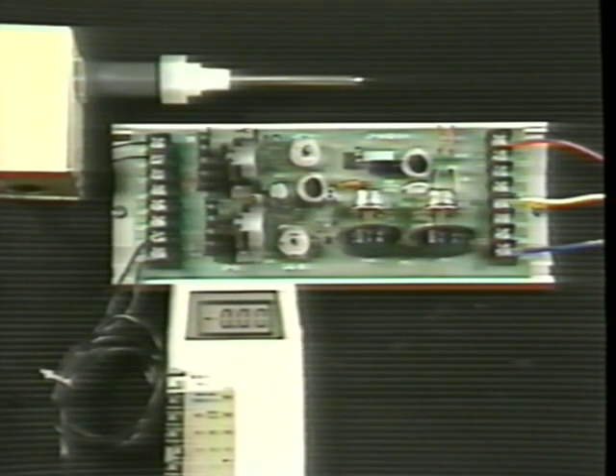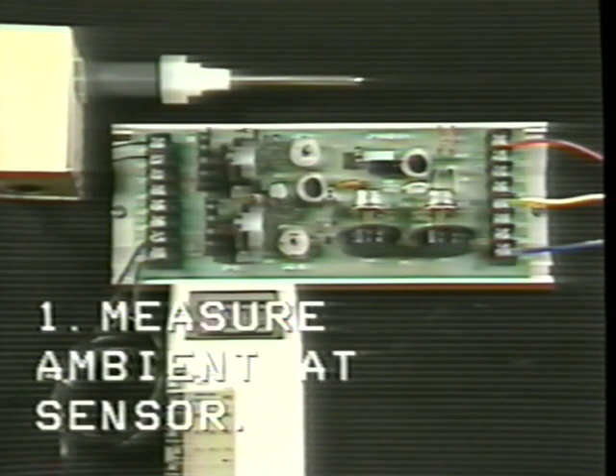Once again, red, 20 volts DC being supplied by the controlled device. Yellow, 1 to 15 volt DC signal coming from the controller. And blue, our common or reference for the voltages. Calibration of the CP8102 is similar to that of any other proportional controller. There are 4 basic steps.